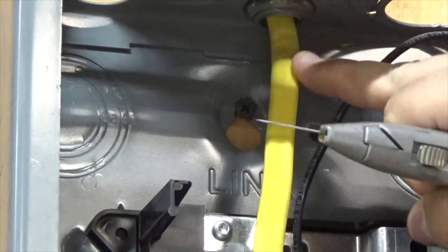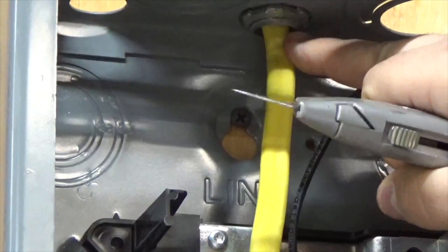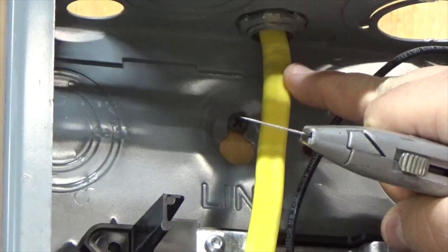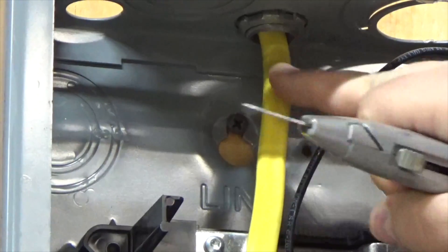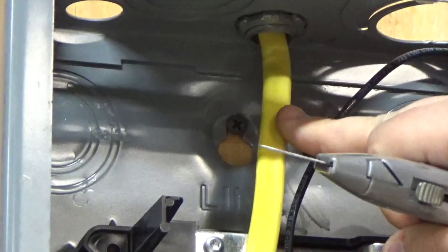Okay, we must have at least a quarter of an inch of insulation coming in entering the box. It can be a half inch. You don't want to go any more than three-quarters of an inch at the most.